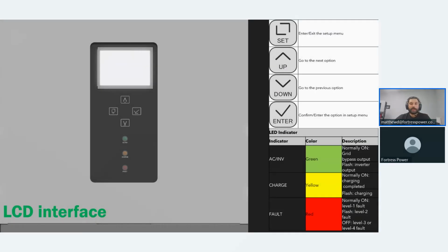Up next, we have the inverter's interface, which is the LCD interface. Okay, you have an LCD on the front of the inverter. Then you have your toggle buttons. You have up, down. You have set, which basically enables the user to go into the settings mode of the inverter. And then you have enter, right? When you're selecting, you select enter to confirm the settings that you want. Then you have the 3 indicators, AC/INV, which is basically inverting, and that should always be green, assuming everything is in normal operation, or if it is in bypass mode, coming from grid to load as well.